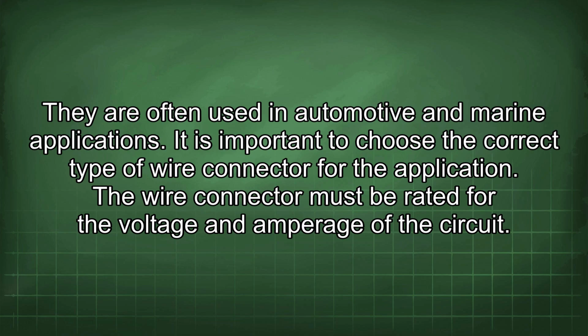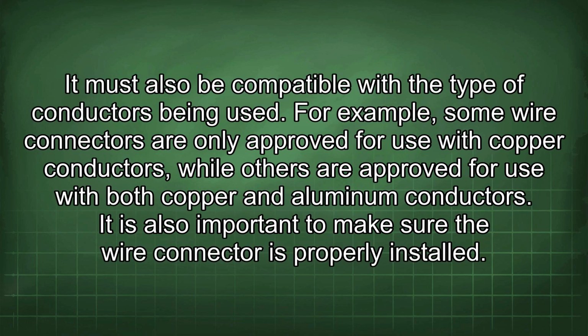It is important to choose the correct type of wire connector for the application. The wire connector must be rated for the voltage and amperage of the circuit. It must also be compatible with the type of conductors being used. For example, some wire connectors are only approved for use with copper conductors, while others are approved for use with both copper and aluminum conductors.